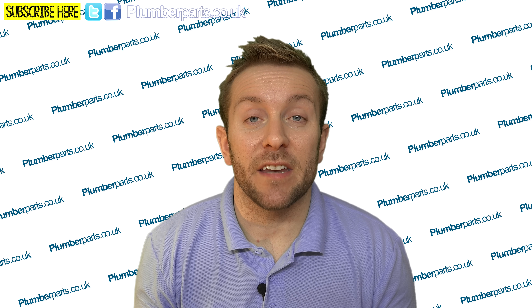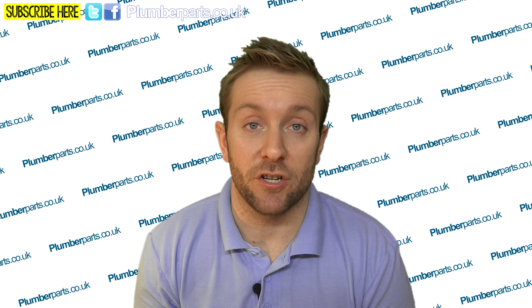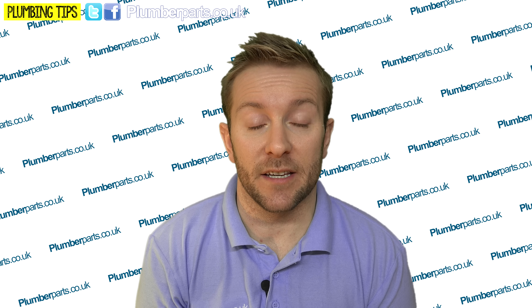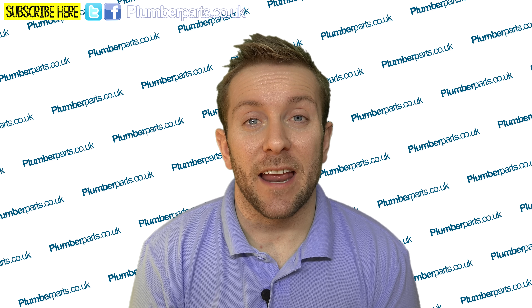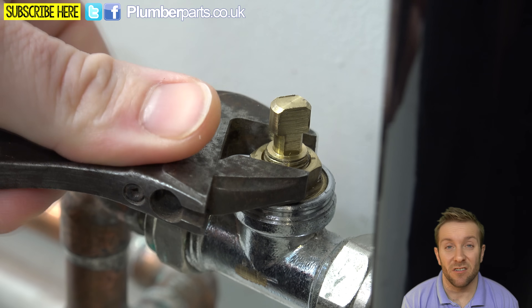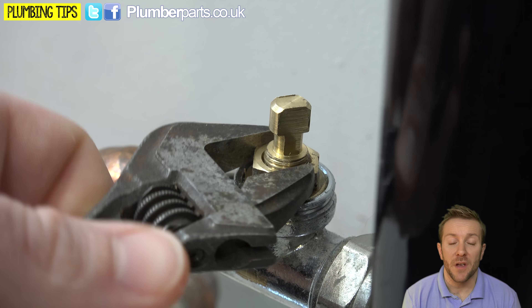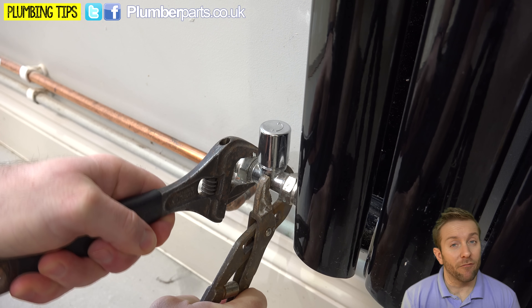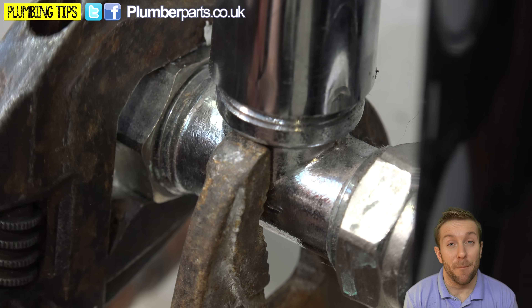Now you've got a basic idea about how a pressurized heating system works, let's look at problem number one that could cause a pressure drop. Most obviously, you could have a leak on your heating system somewhere. When it comes to finding leaks, the best thing to do is pop around all the radiator valves and just make sure there's no leaks on them. Make sure you lift up the heads as well to check there's no weep on top of the valves. Make sure the compression fittings on each side of the radiator valves are nice and tight and there's no water anywhere.